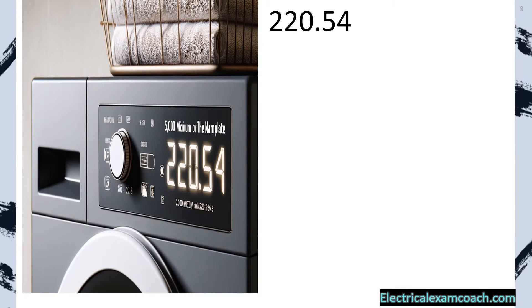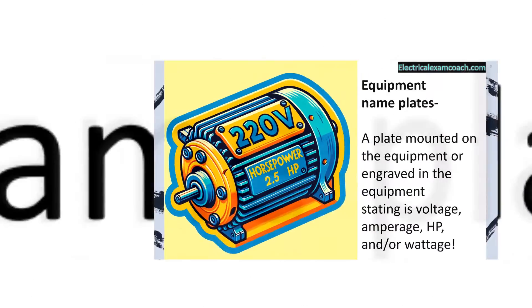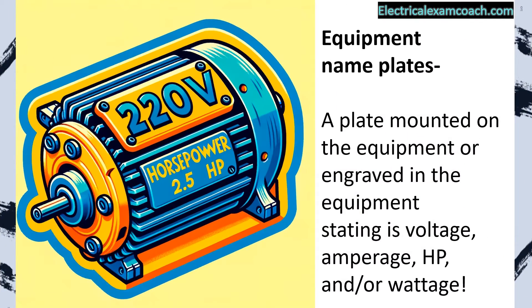Section 220.54 lets us know that dryers must be calculated at a 5,000 VA minimum or the nameplate rating, whichever is greater. An equipment nameplate is a plate mounted on or engraved in the equipment stating its voltage, amperage, horsepower, and/or wattage. It may only have a few of these, but as we've learned in previous lessons, we can apply Ohm's law to find the unknown.